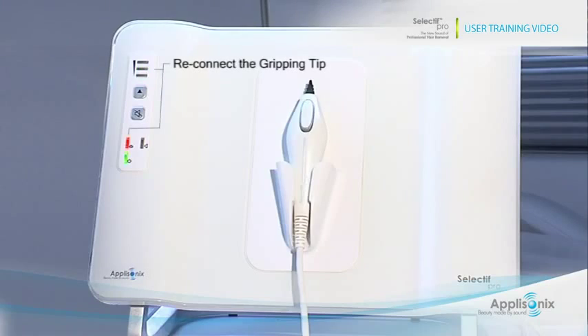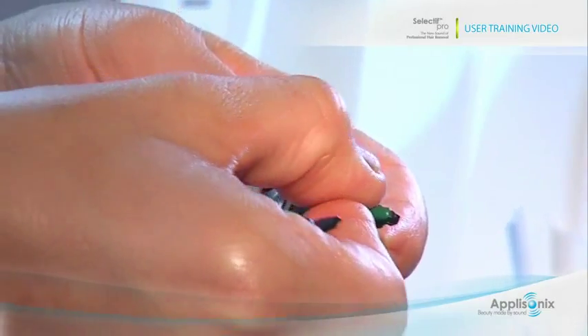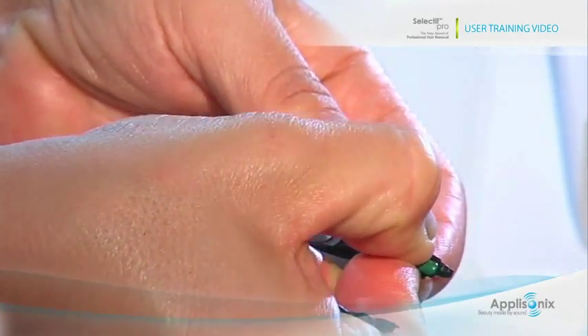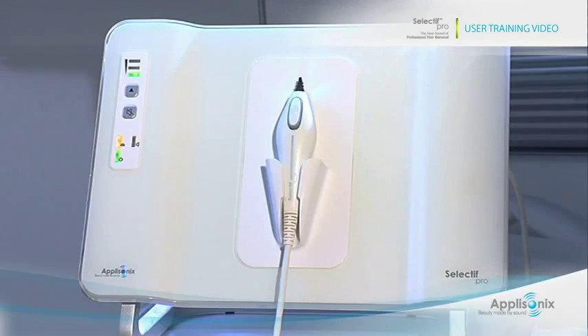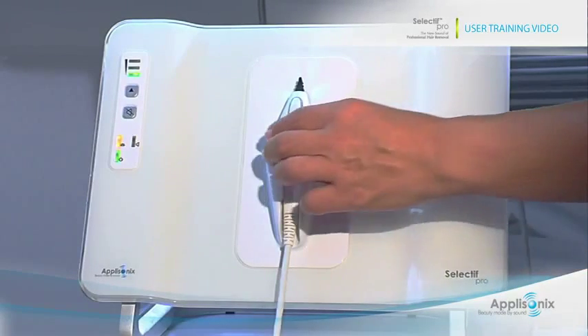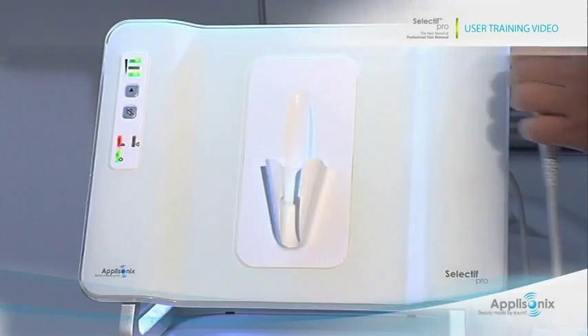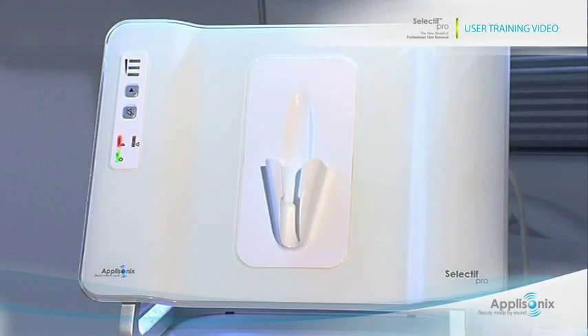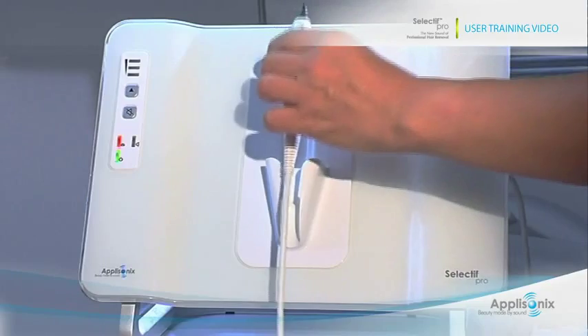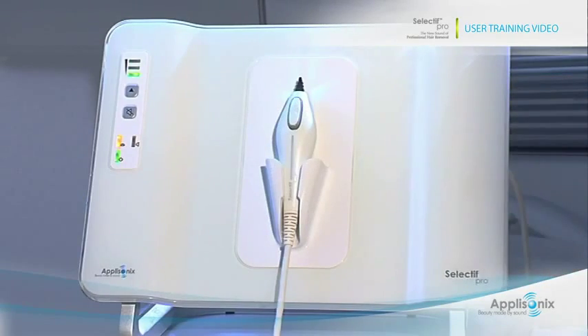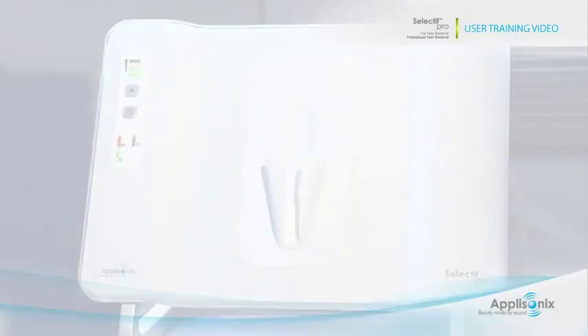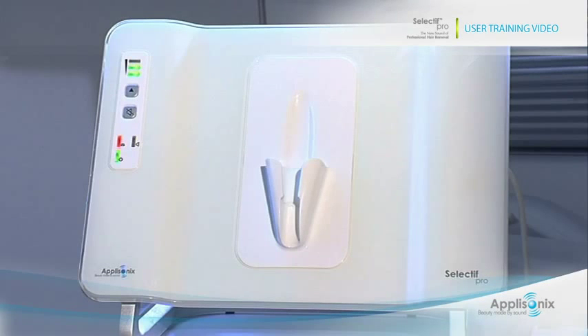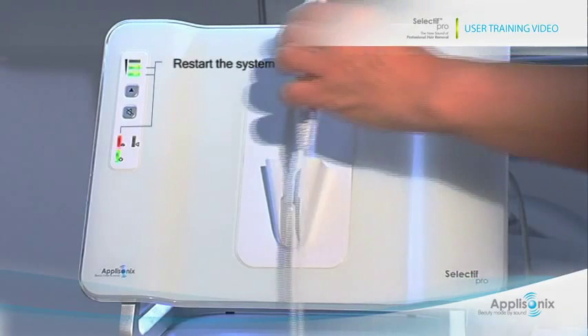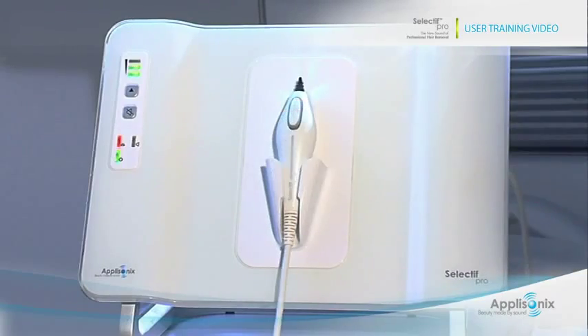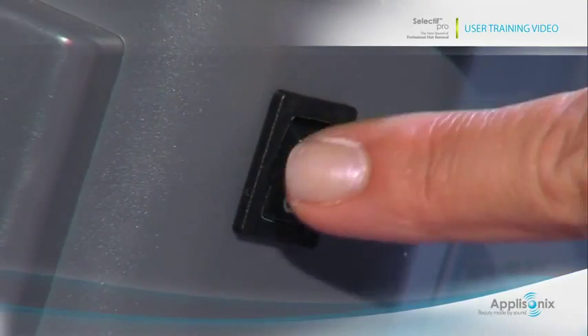When the status light is red and B mode is blinking, the gripping tip is disconnected. Connect a new gripping tip according to the instructions. During self-test and calibration, the probe should be in its holder. If you remove the probe before final calibration, you will notice the status light red and the mode A and C lights blinking. Place the probe back in its holder. When the status light is red and the A plus B mode lights are blinking, there is a probe or pulse malfunction. Return the probe to its holder, restart the system, and wait for calibration to end.